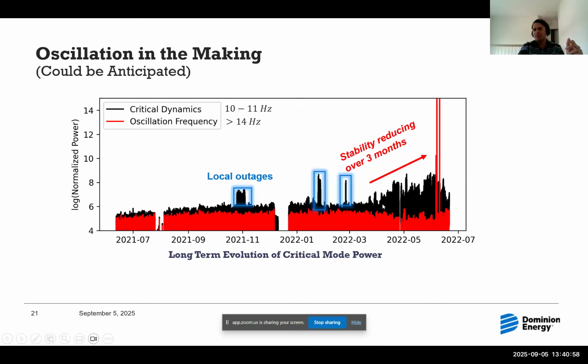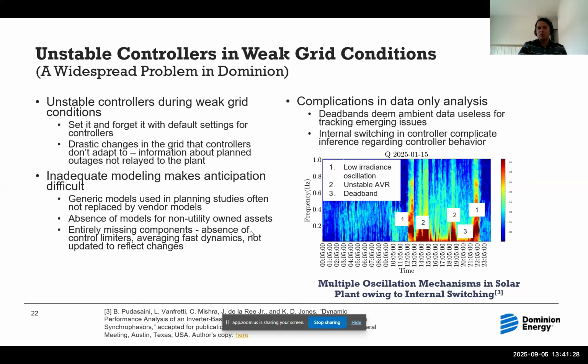So you can see how this is gradually increasing, and eventually you see oscillation, which tells us that we had almost 3 months to track the evolution of this particular mode. We could have taken decisions on time, instead of waiting for the system to tell us when to, or being reactive and solving it as a root cause problem. This problem is very common, so this is not an isolated incident.